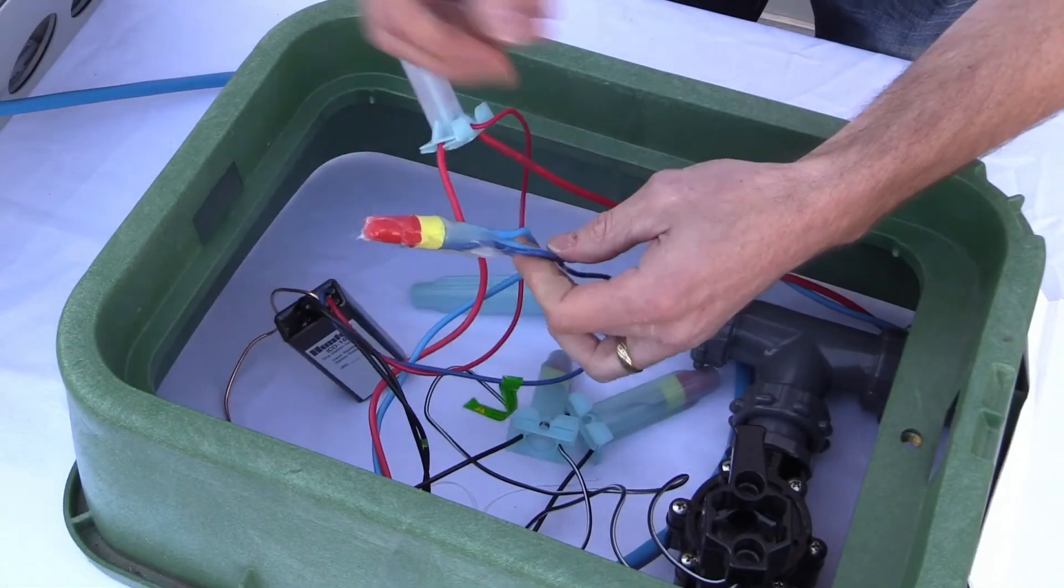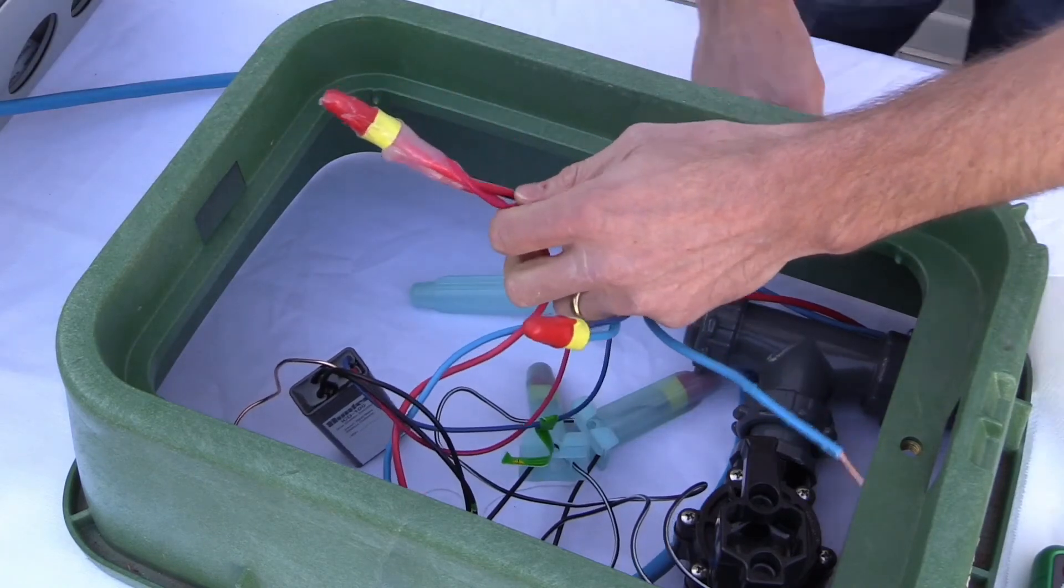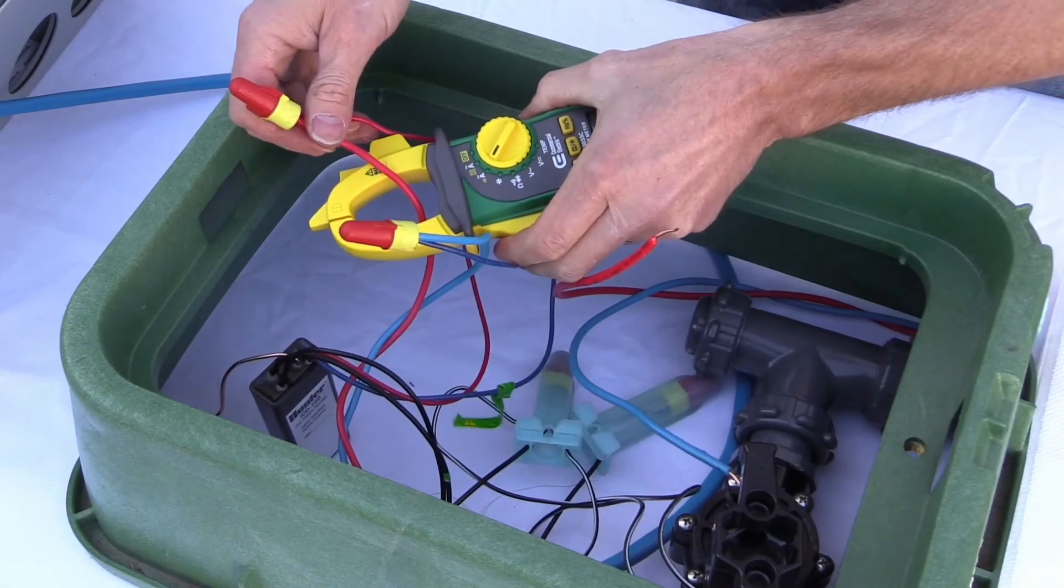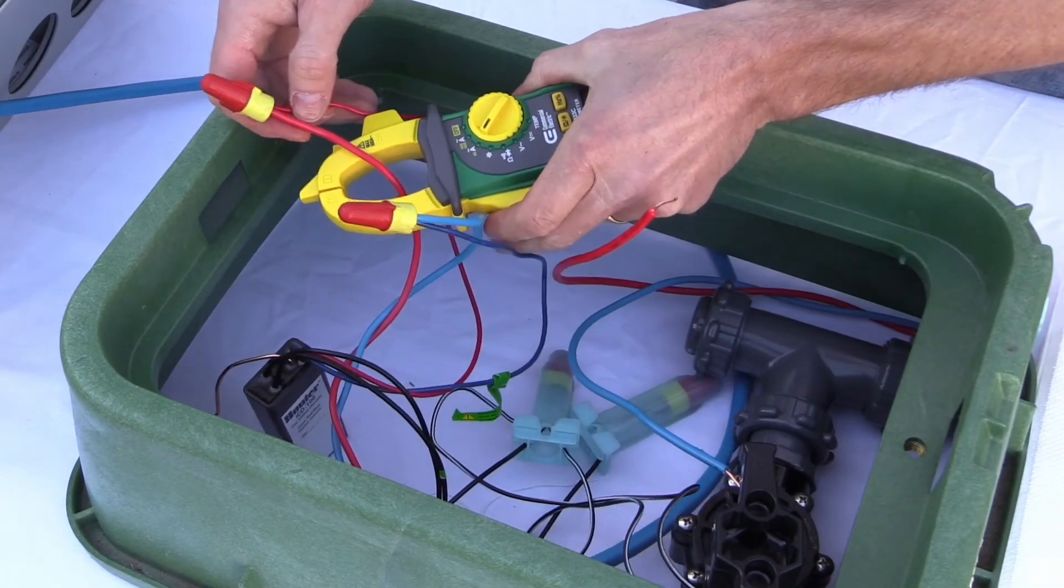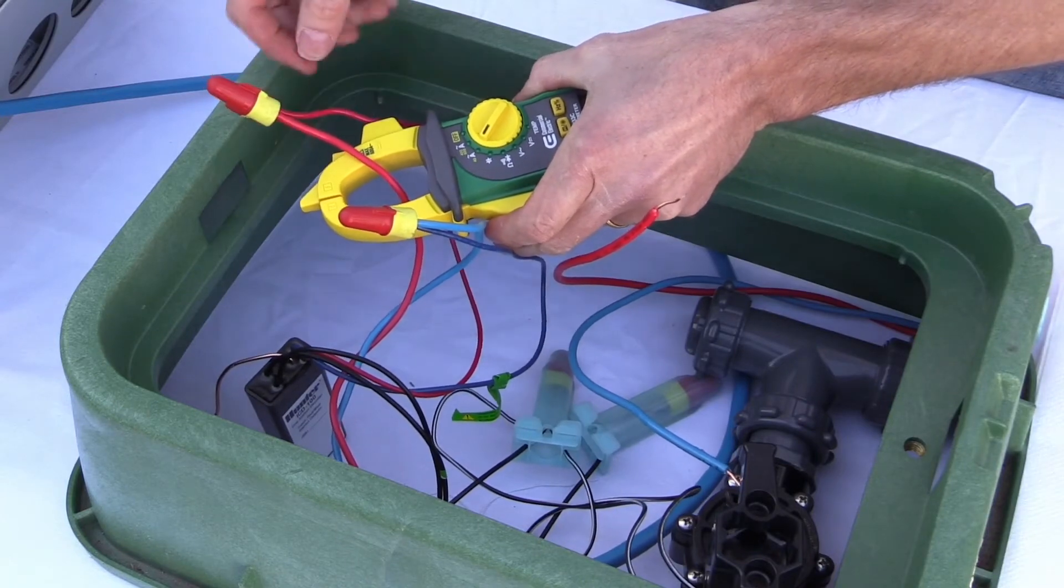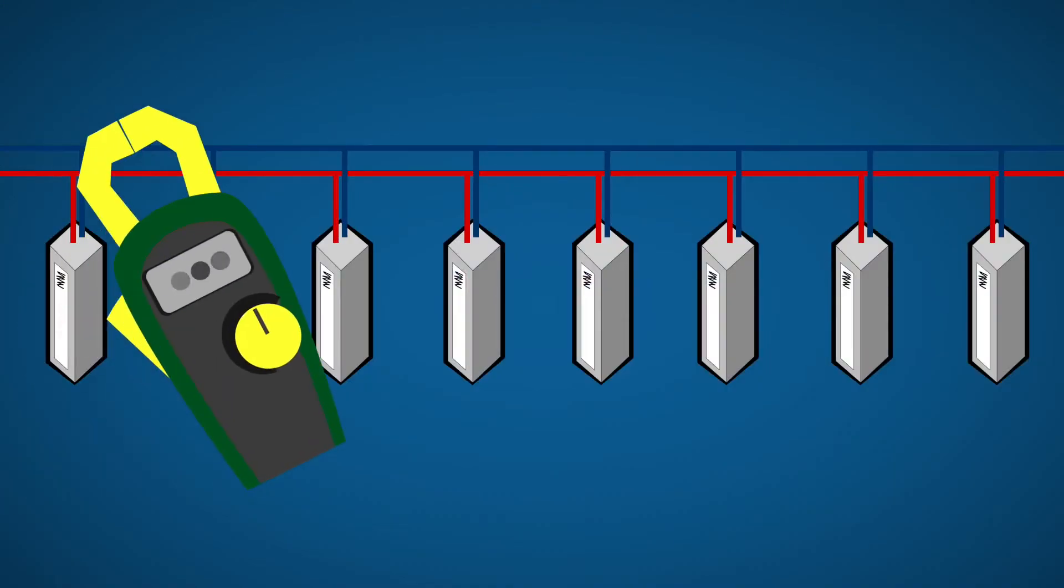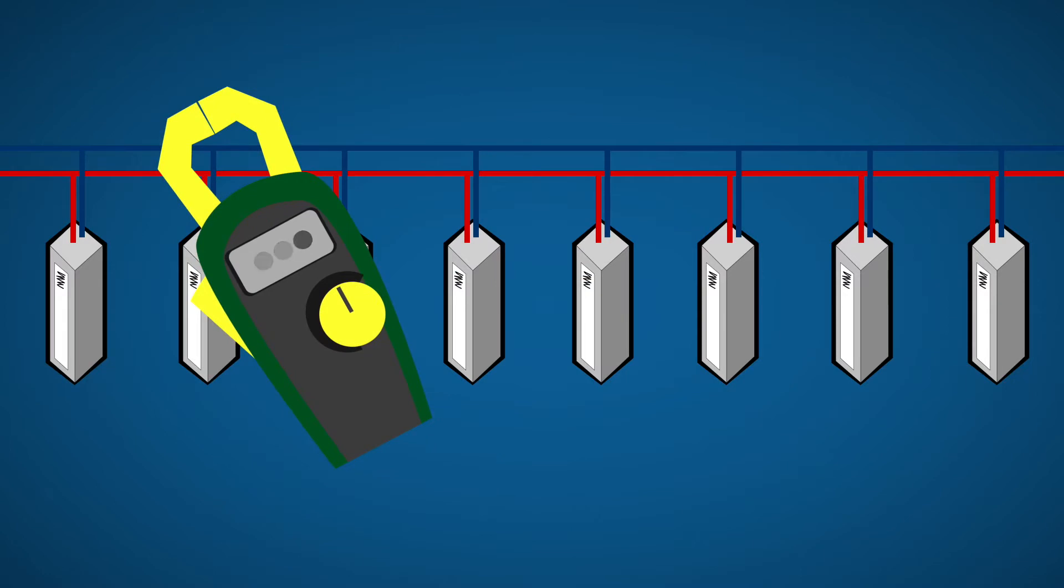Once you know what leg to work on, go halfway down the cable path and disconnect the second half. Test again to see if the short is resolved and is therefore isolated to the section you've disconnected. If it has, then you know where to focus further testing and disconnecting.